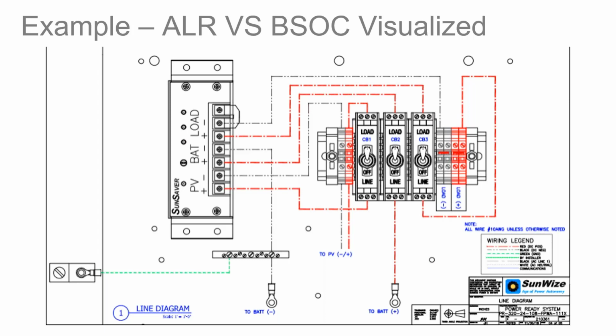This system uses Class 1 Division 2 breakers, as we noted. However, if it's not desired or needed, you can use Class 1 Division 2 fuses and fuse holders to save a little money, but it does make maintenance and troubleshooting a little bit less convenient.